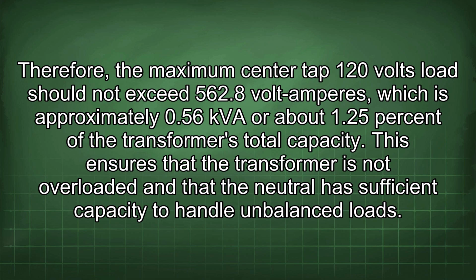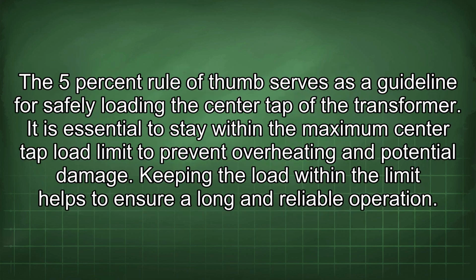Therefore, the maximum center tap 120 volts load should not exceed 562.8 volt-amperes, which is approximately 0.56 kVA, or about 1.25% of the transformer's total capacity. This ensures that the transformer is not overloaded and that the neutral has sufficient capacity to handle unbalanced loads. The 5% rule of thumb serves as a guideline for safely loading the center tap of the transformer. It is essential to stay within the maximum center tap load limit to prevent overheating and potential damage. Keeping the load within the limit helps to ensure a long and reliable operation.